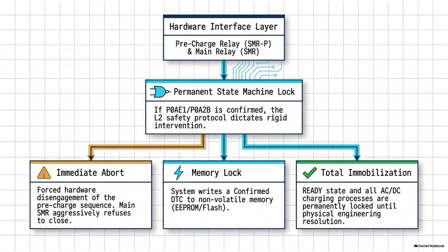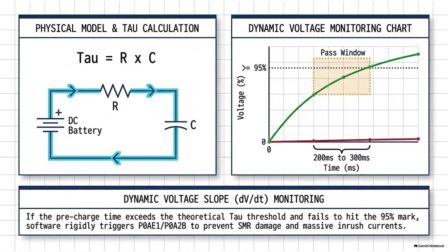And the resistor will eventually fail, but what the documentation highlights here is that the electromechanical relay itself begins to structurally fail under that thermal load. Wait, really? The relay melts? It's the metallurgy. The relay contains return springs, usually a beryllium-copper alloy, and they're designed to pull the contacts apart when the power is cut. But if the ambient temperature inside the relay spikes from that continuous overcurrent, those springs reach their thermal annealing temperature. Oh, meaning the crystal structure of the metal relaxes. Yeah. The spring loses its tensile strength, it loses its elasticity.